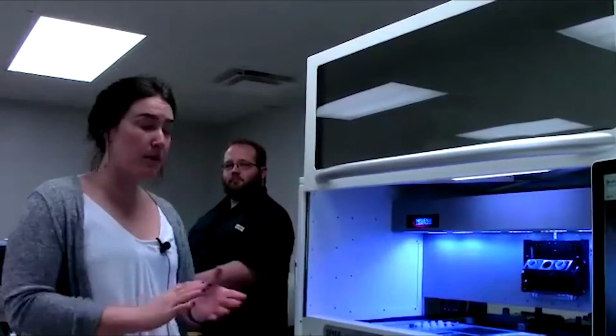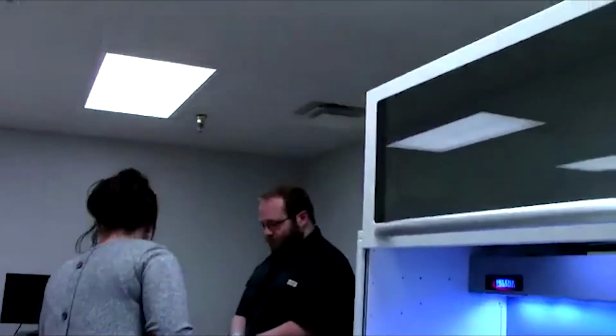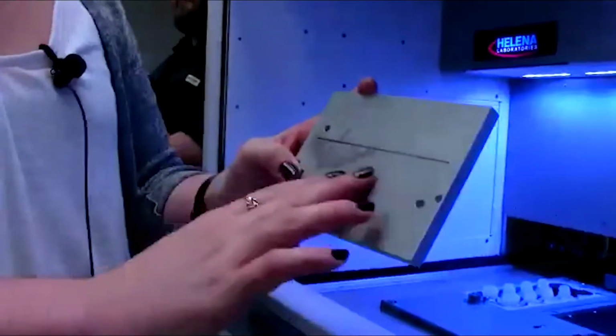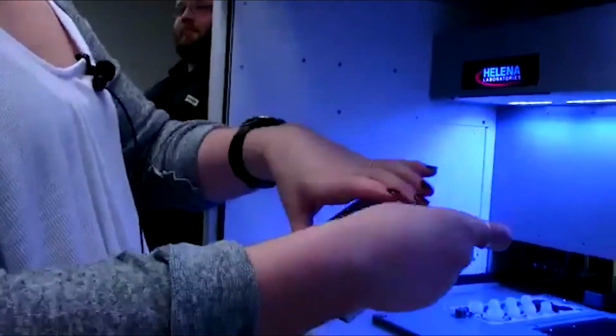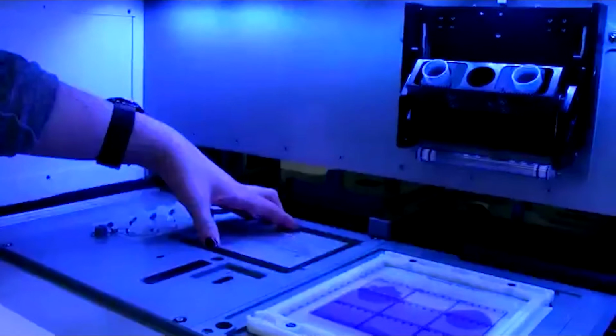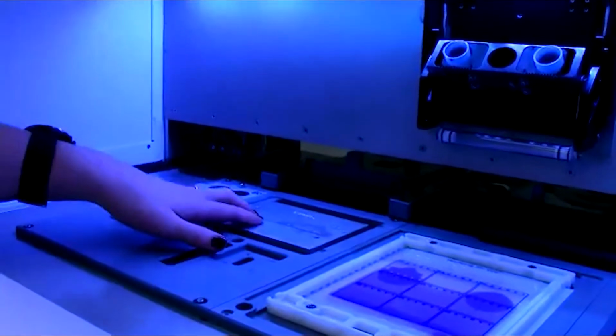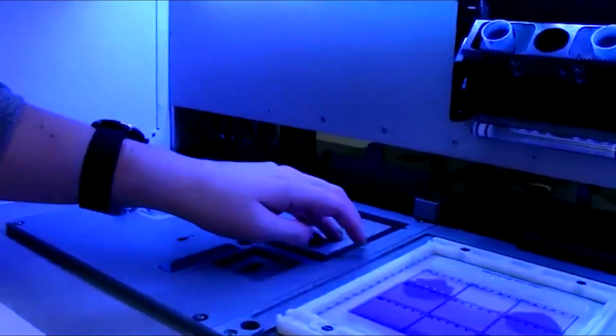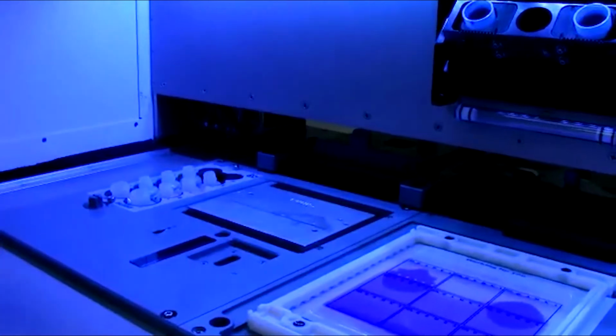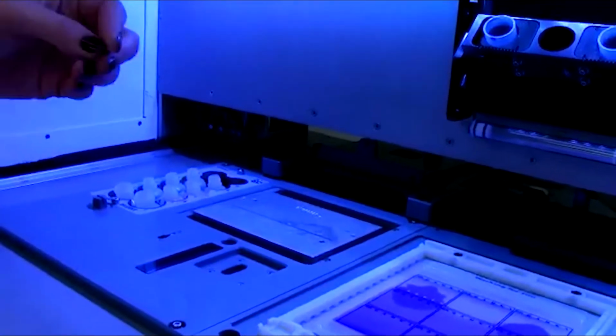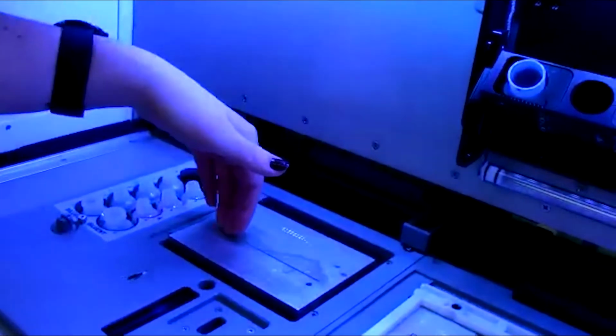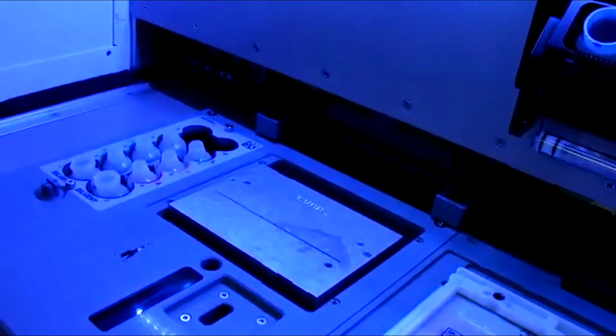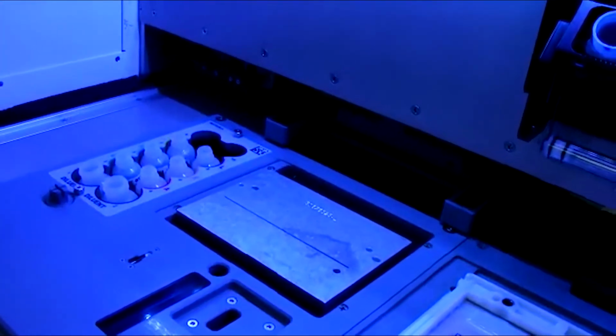Yeah. All right, so some of the calibration jigs. This one I've used quite a bit and it's got a little stain on it, but don't mind that. This will slip very nicely into your sample tray station here. You'll notice it has a groove, and you're just checking to make sure that a blade in the center slot of your applicator falls directly into that groove. So that's how you would calibrate that position.